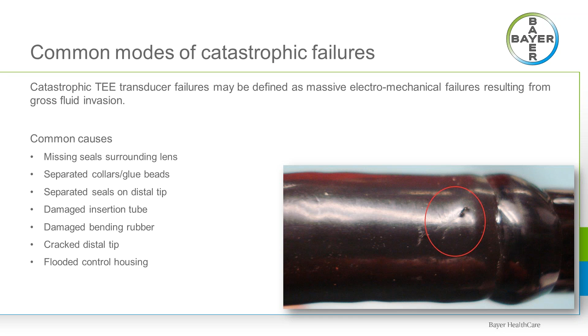So, probe manufacturer, let's jump back there. It's common for the distal tip to become scratched over time as a result of continued normal use. That tip is going across the molars, across a bite guard. It's maybe impacted during some cleaning and handling sessions. So you can expect the tip to become scratched over time. But deep gouges and cracks resulting from trauma, in combination with the disinfection process, can also result in these costly, catastrophic failures.